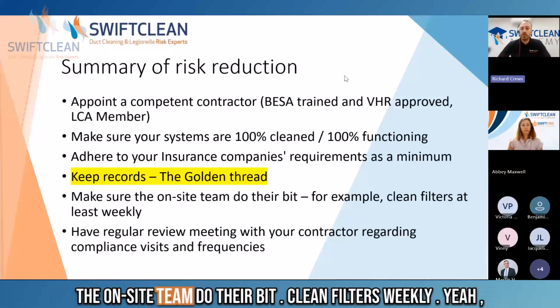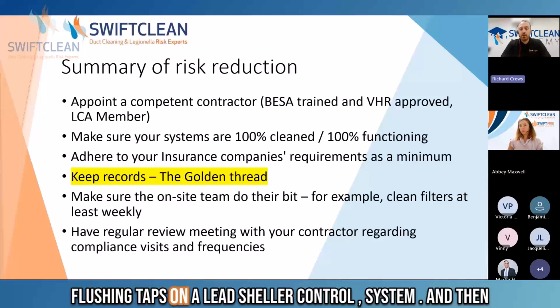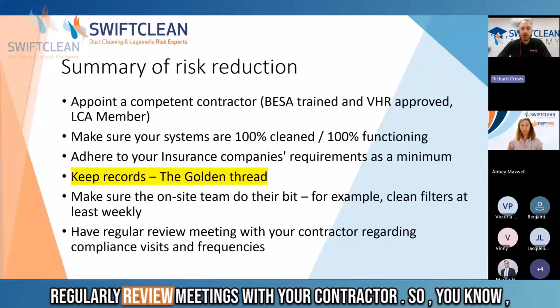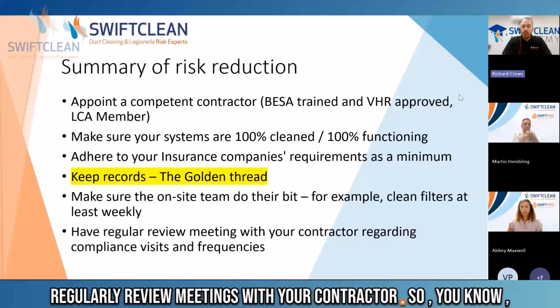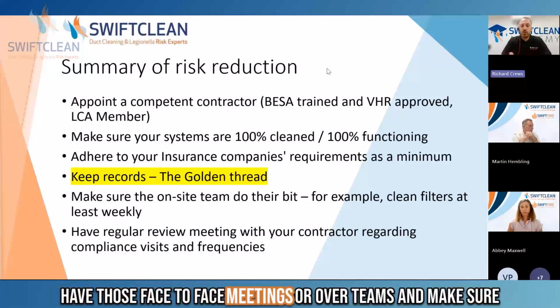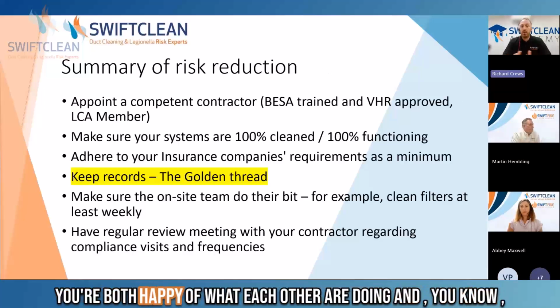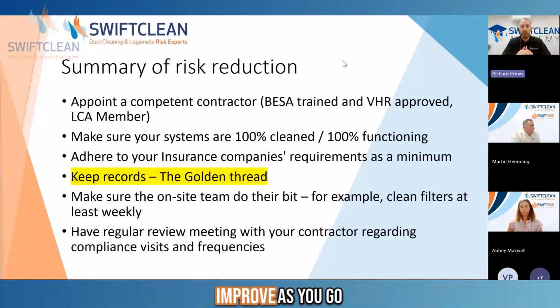Make sure the on-site team do their bit: clean filters weekly, flush taps on a Legionella control system, and then regularly review meetings with your contractor. Have those face-to-face meetings or over Teams and make sure you're both happy with what each other are doing, and improve as you go.